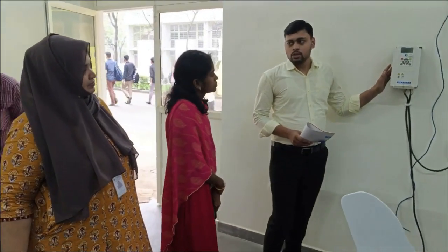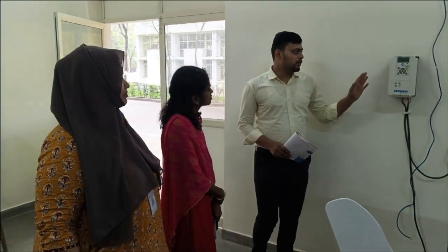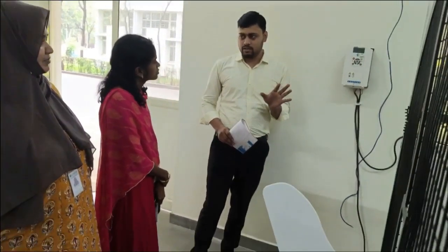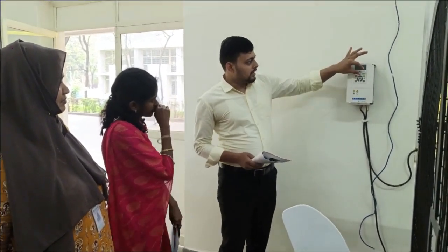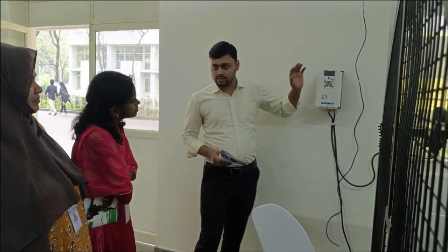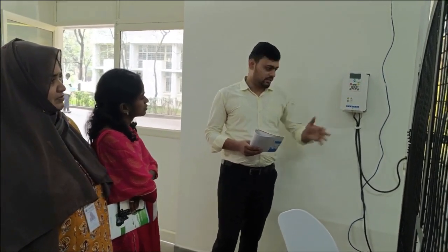Firstly, I will define this variable frequency drive, whose rating is 15 kilowatt and which goes from 0 to 60 hertz frequency. In this system we are going up to 25 hertz frequency, because at 25 hertz we get the rated output of the wind turbine power. And this is the part where we control the frequency. You can move it in the clockwise direction and increase the frequency step by step.